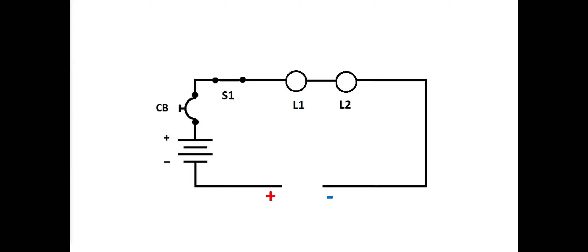In summary, in a normal circuit, when the circuit breaker is in and the switch is open, the difference in potential exists at the switch. When the switch is closed, the difference in potential moves from the switch to the load. If the circuit breaker is pulled, the difference in potential moves from the load to the circuit breaker. If the circuit breaker is in and the switch is closed, but an open occurs, the difference in potential moves to the open. The open is found by identifying the positive and negative potentials when testing terminals. The point where they meet is the location of the open.